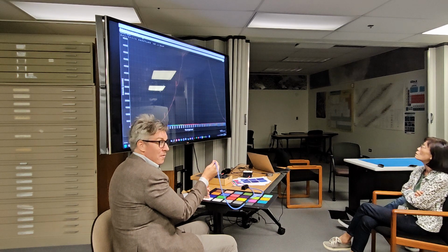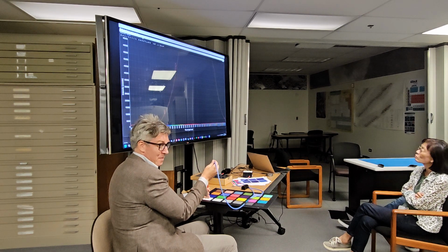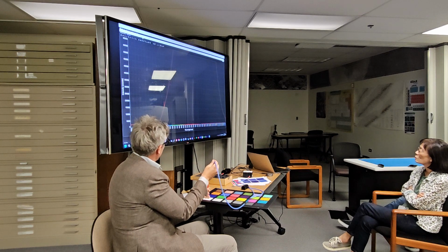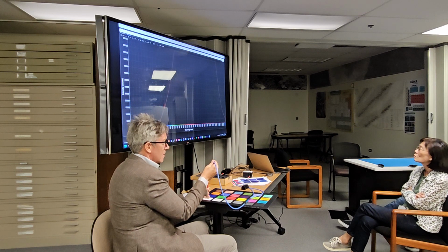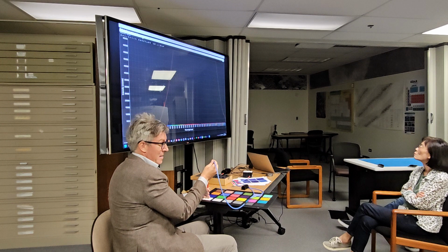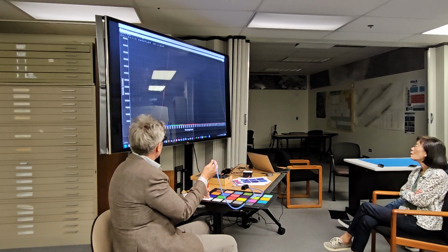It exceeds the number of counts. It exceeds the dynamic range of the instrument, right? You see that flat bar at the top? It just flattens out at the top, right? It hits 65,000 and it just reports 65,000.